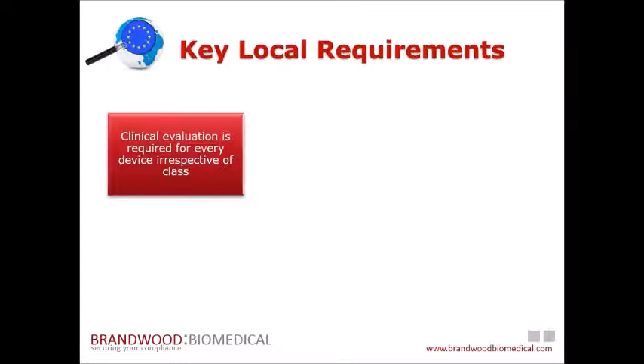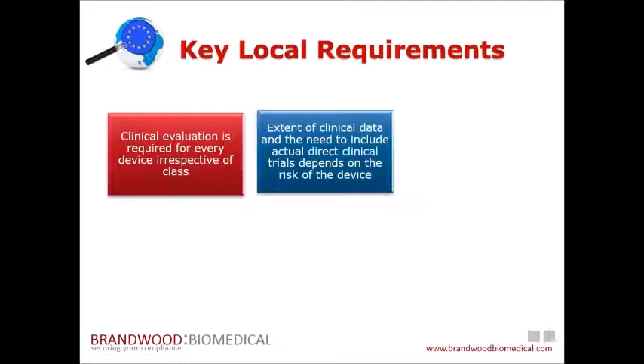Now, to sum up, well, not to sum up, I guess some of the key local requirements in Europe I've got here is, firstly, clinical evaluation is required for every device, irrespective of the classification. As I'll mention later on, it's different in China, for example, where Class 1 devices don't require clinical trial data. But in Europe, whether it's Class 1 or Class 3, you must have clinical evidence data or a report. The extent of clinical data is normally dependent on the risk of the device. So if it's a low risk or Class 1, obviously, the requirements for clinical data will be lower than for a high risk device.